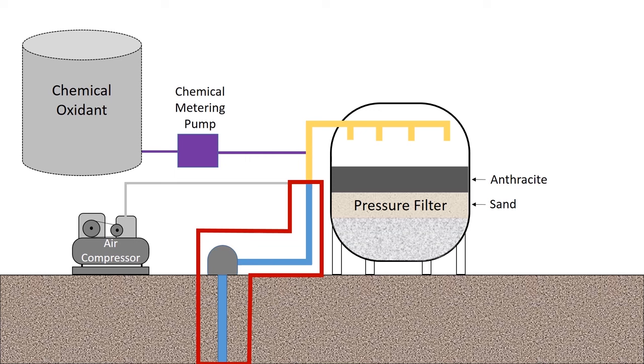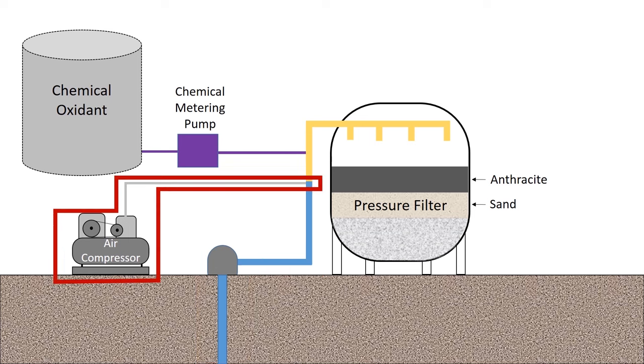So what we want to do while it's still in solution is we oxidize it. There's a couple ways we can do that. We can use an air compressor and inject air, which contains oxygen, into the flow stream, which would cause oxidation. So we're on purpose trying to get the iron and manganese that's in solution to precipitate out of solution so we can filter it out.